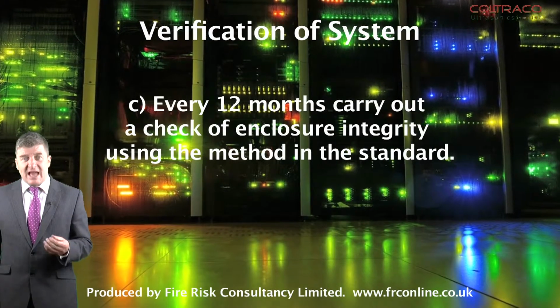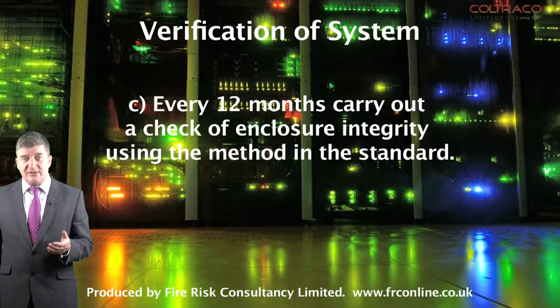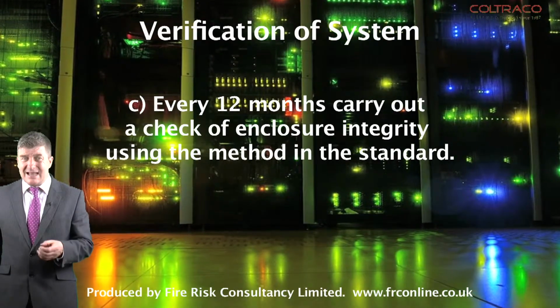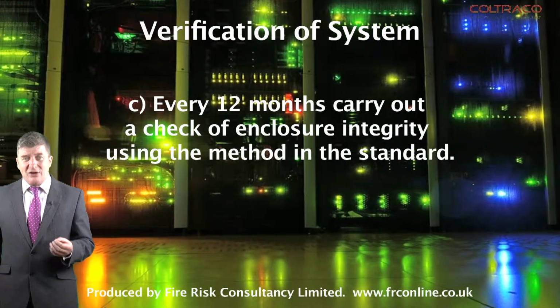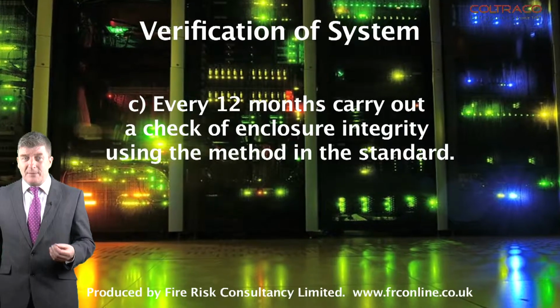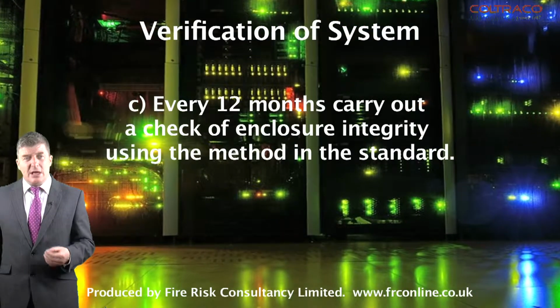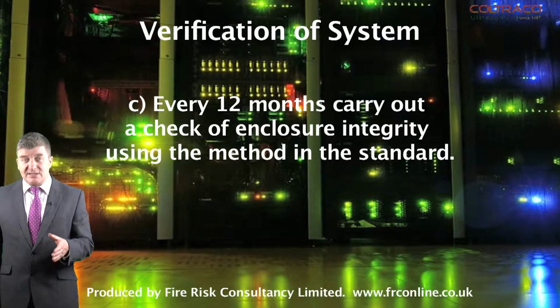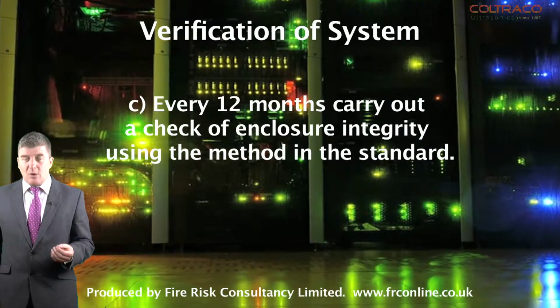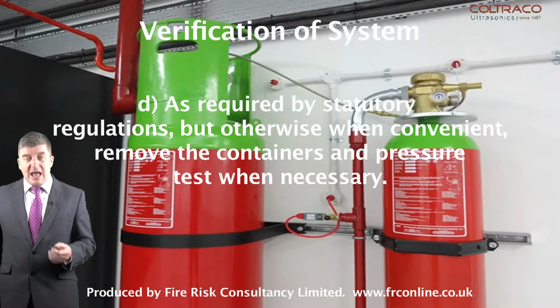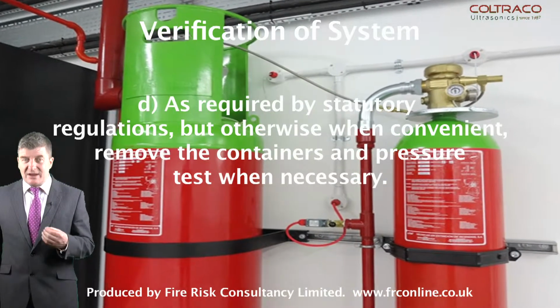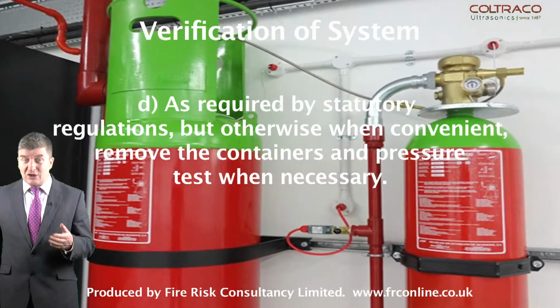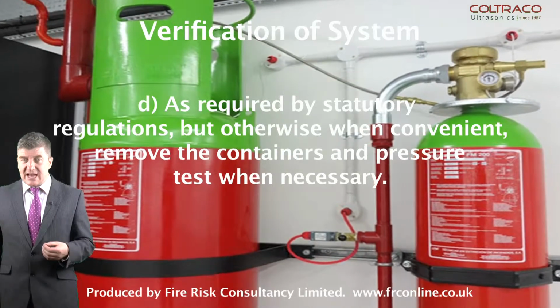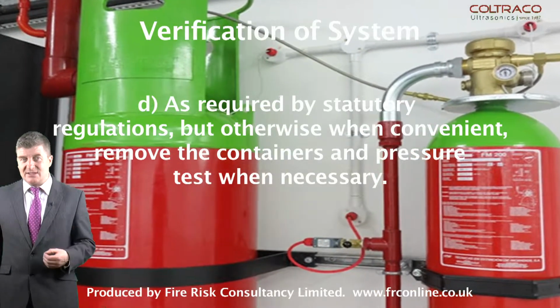Every 12 months carry out a check of enclosure integrity using the method in the standard. If the measured aggregate area of leakage has increased from that measured during installation, which would adversely affect the system performance, carry out work to reduce the leakage. As required by statutory regulations, but otherwise when convenient, remove the containers and pressure test when necessary.